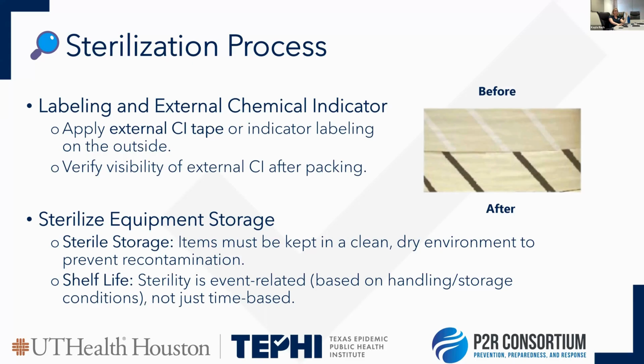They've cooled down, and you can safely transport them to the sterilization or the sterilized equipment storage area, that it's clean, dry, it has maintained temperature, humidity, and then it's organized.